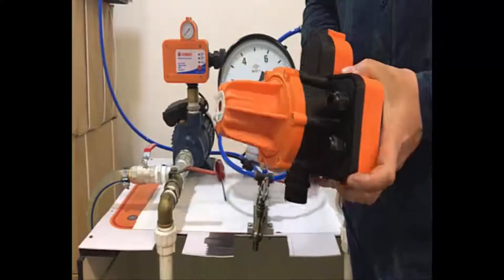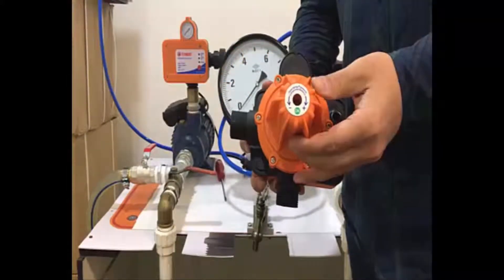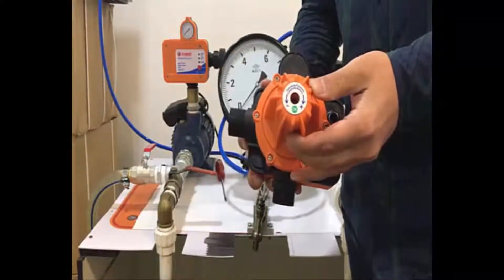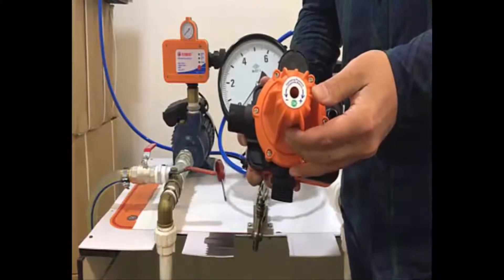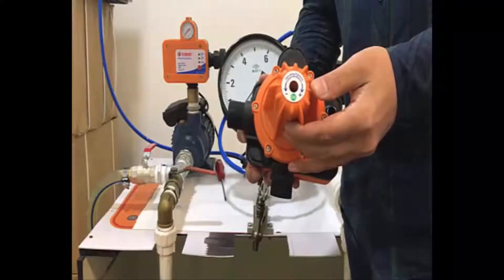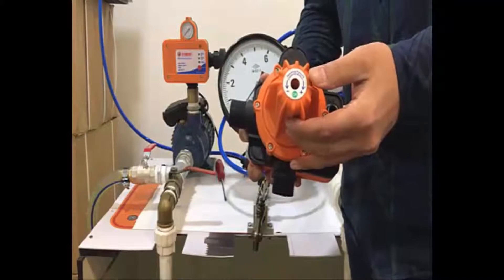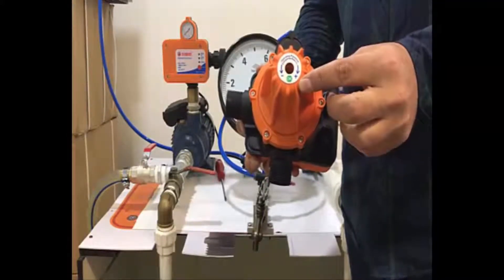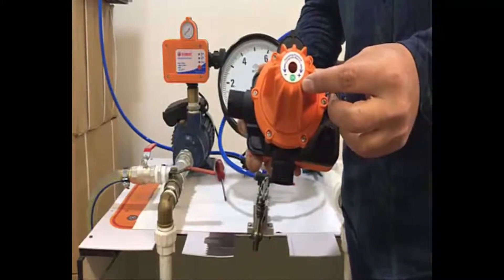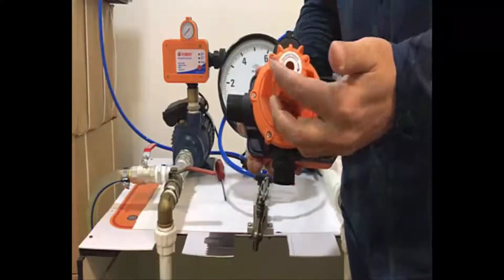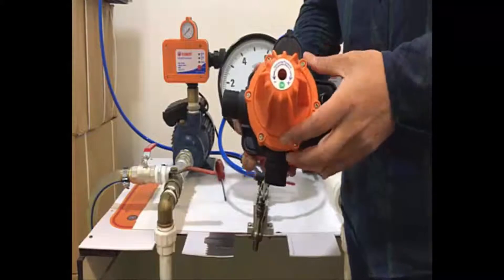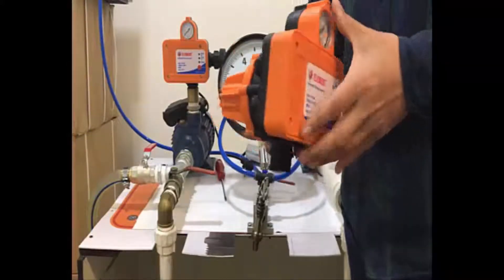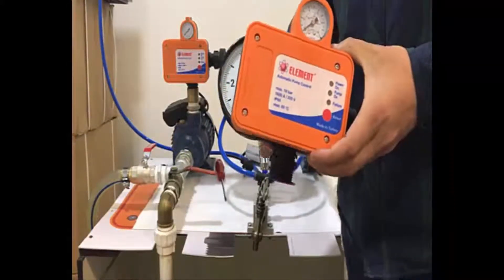As you can see, there is an adjusting screw at the back side of the device. The pressure level of the restart can be increased by screwing the screw clockwise to the direction of the plus sign, and can be decreased by unscrewing it counterclockwise to the direction of the minus sign. Now, let's see how our device will be set for the first installation.